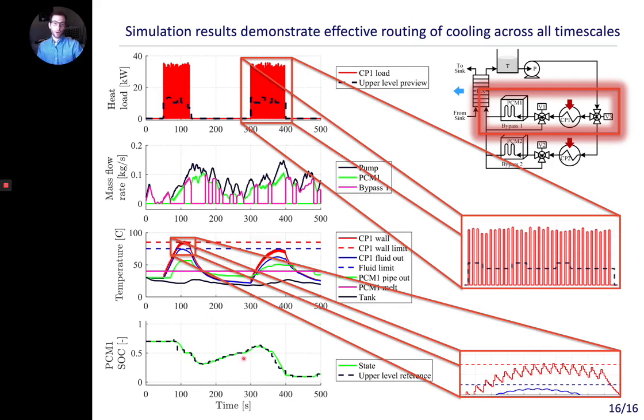However, what our controller is doing very intelligently is building up some thermal storage in our PCM so that during this second period of high loading, when we know this temperature is going to spike, we have the ability to cool that off. Again, this temperature doesn't achieve its upper bound, but that's somewhat due to coupling with the other loop of the system, which is also at this time getting rather hot.